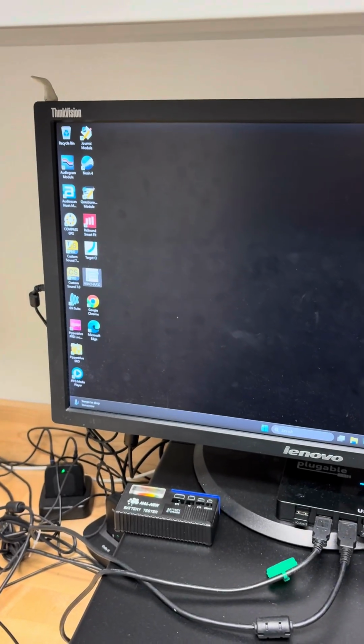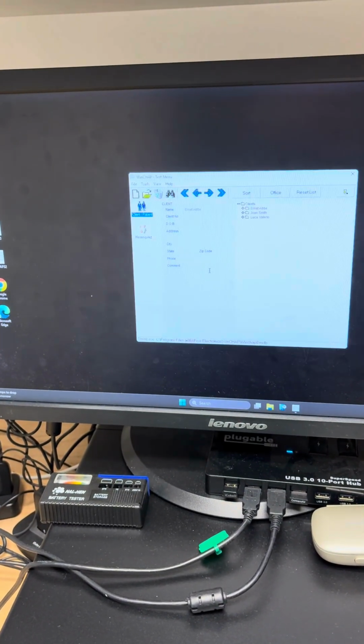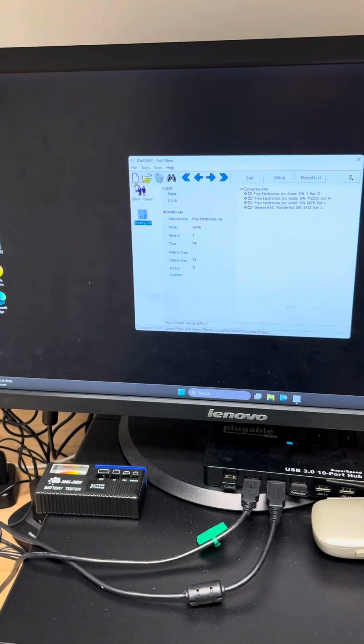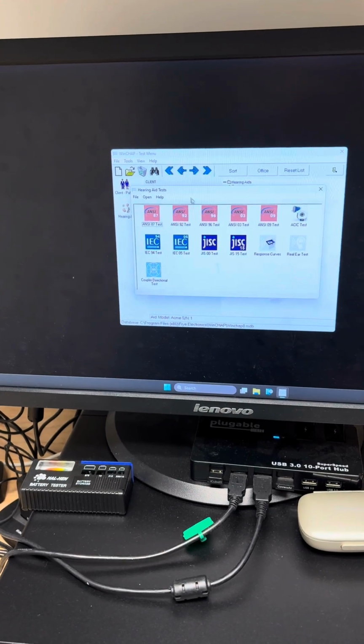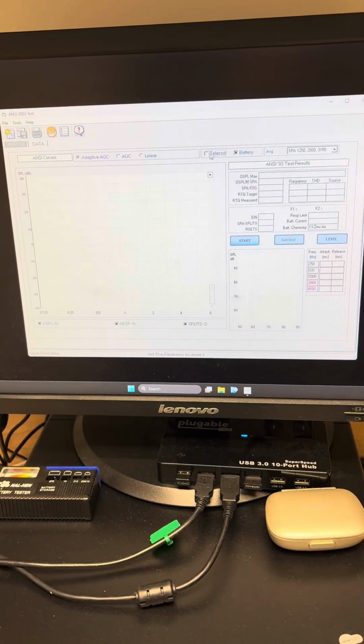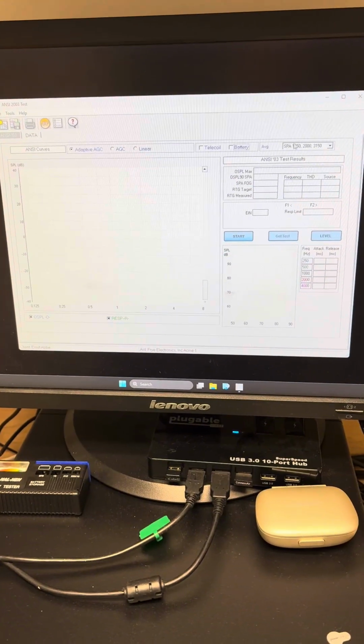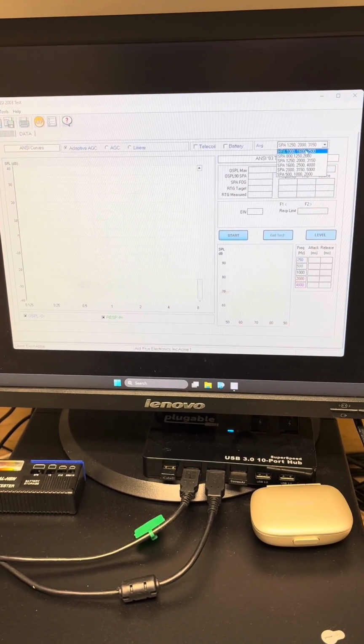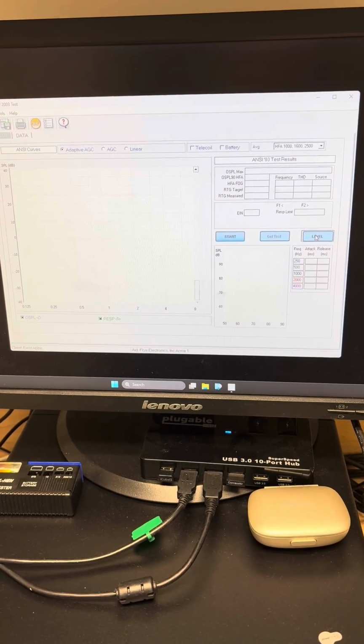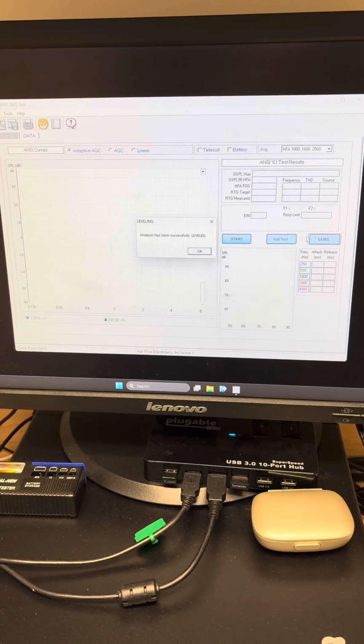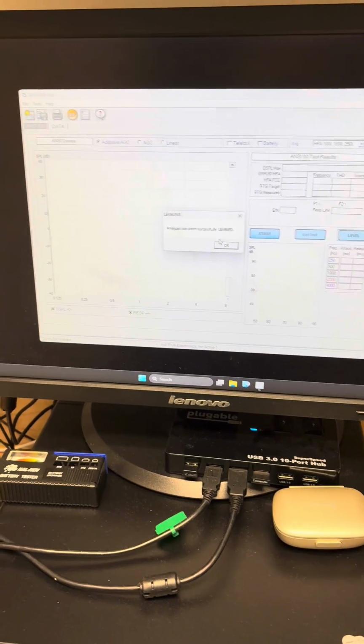Over to the computer, we are opening WinCHAP, clicking test menu, hearing aids, and this blank sheet of paper, and we do ANSI03. Unclick anything that doesn't apply to your hearing aid that you are going to test. HFA is selected, and hit level. And it has been calibrated.